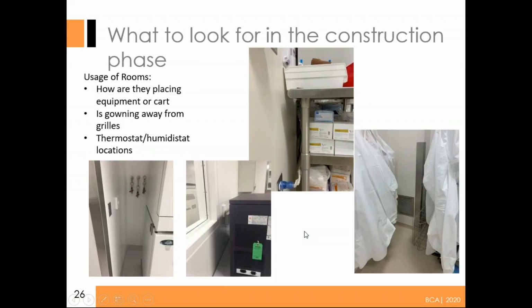Here's where we talk about when the users are going to be putting their equipment in. Here's your typical: thermostat, humidistat, thermostat, humidistat. Now here's one we found in the pharmacy when we came back for a warranty issue. They were having some weird pressure issues, so I just sat in the room and watched them for an hour and found that they were putting carts up against these low returns, and you can see the plastics getting pulled into it. And then the gowns were actually being pulled into the returns, affecting pressurization.